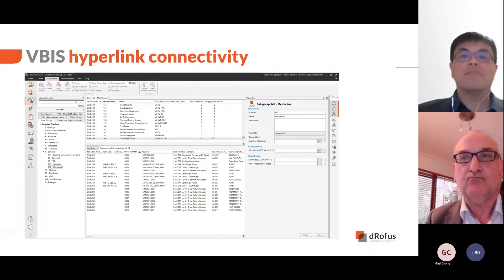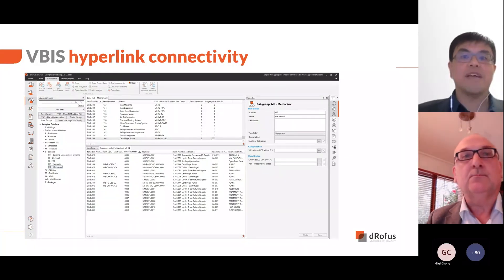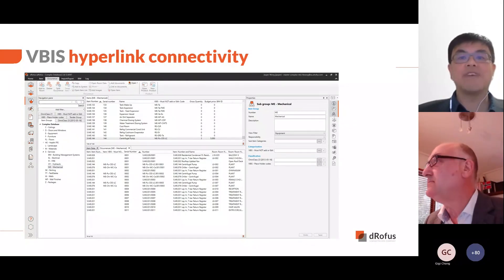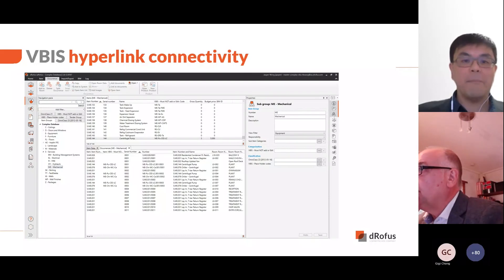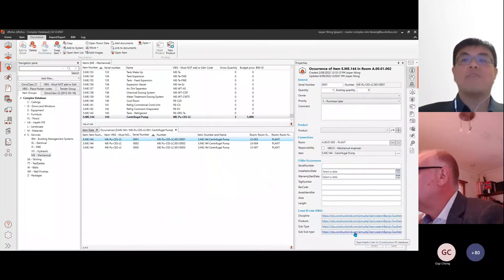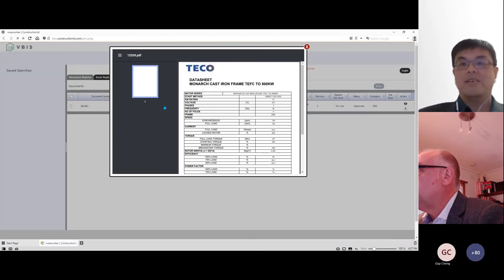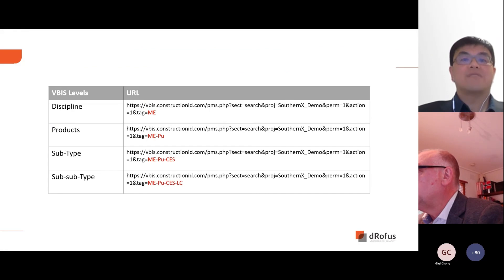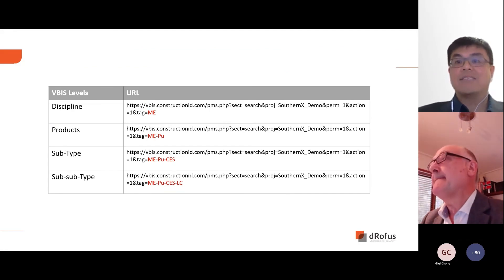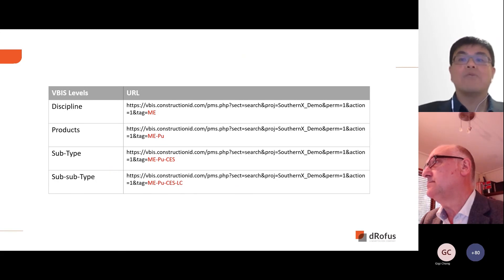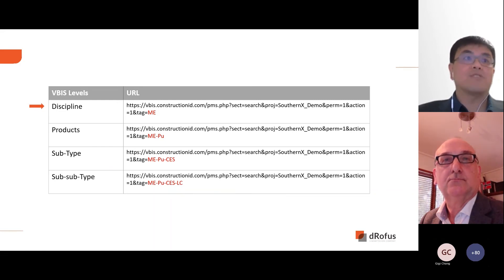Moving on to connections through hyperlinking. The dRofus software can concatenate different attribute field values, providing flexibility and the ability to create custom values a project may require, such as unique codes or URLs. We will now demonstrate the second aspect of VBIS, which is creating a search syntax to get asset data from a different system. This centrifugal pump has a four-level VBIS code. Selecting the occurrence shows four URLs linking to an external system containing more data and information. Each URL is created dynamically and filters the external database for the required information. The syntax is made up of static parts and dynamic parts, so if you select an element with a different VBIS code, the URL will filter the displayed information of the external website based on the VBIS codes.